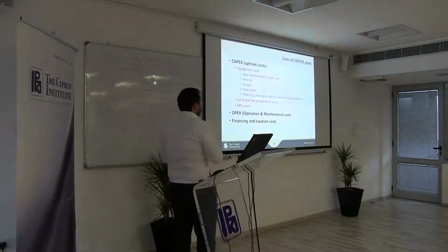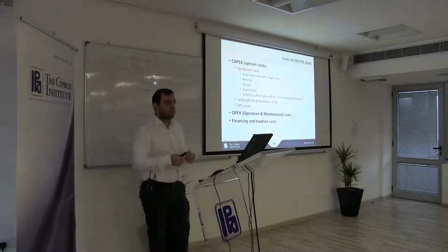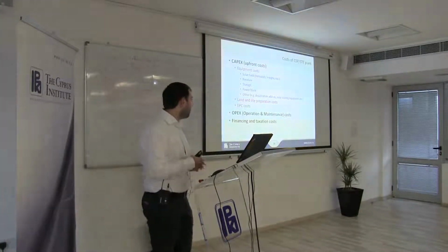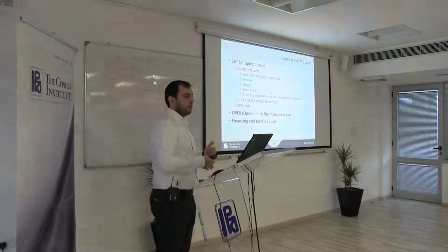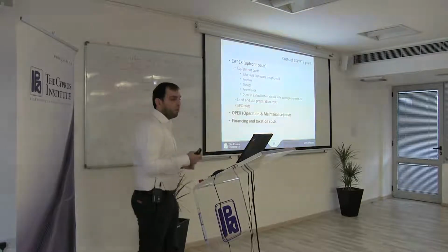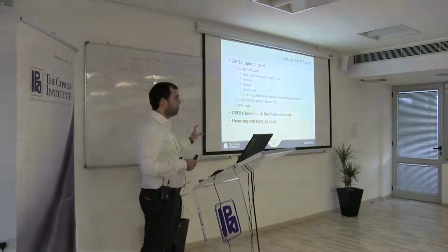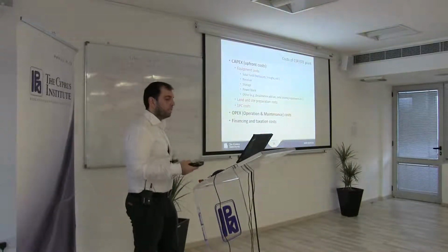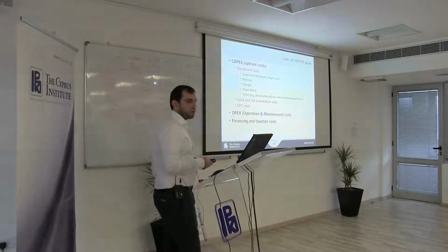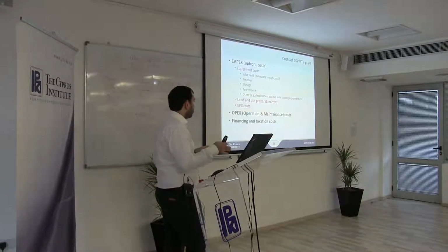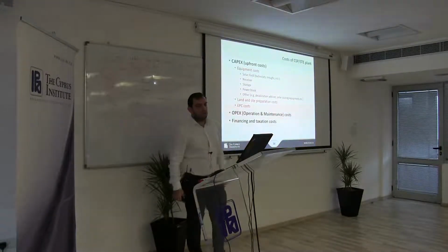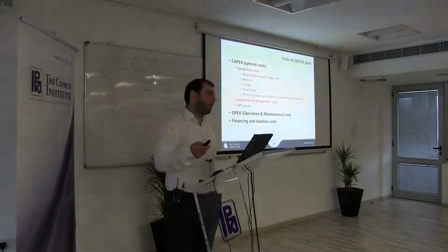The different types of costs that characterize CSP and solar thermal plants. Basically, we have capital expenditure, so upfront costs, the costs that we have in order to put the power plant in place. And this can be further broken down into equipment costs. In the case of CSP, it's, for instance, the solar receiver, the solar field, the storage system, the power block, and potentially other components, such as a desalination add-on, in case it's a cogeneration plant for electricity and desalinated water generation, or cooling equipment. Then we have land and site preparation costs, so we need to prepare the site before we bring in the equipment and install it. And we have engineering, procurement, and contracting costs that are often characterized as indirect capital expenditure costs.